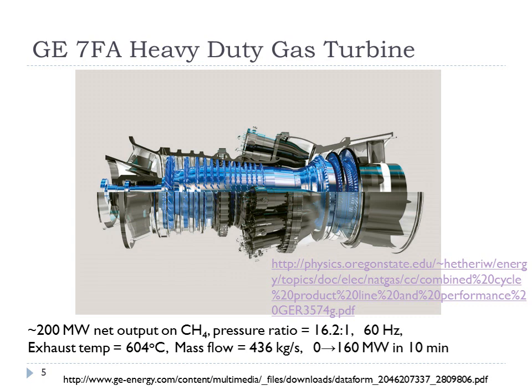GE quotes that this turbine can go from 0 to 160 megawatts in 10 minutes. This is what I meant before — if you owned one of these turbines, you could get paid for just sitting around doing nothing but promising to turn on during a blackout or times of high demand. These hot exhaust gases at 600°C are often coupled with Rankine cycles to generate additional electricity via steam turbines.